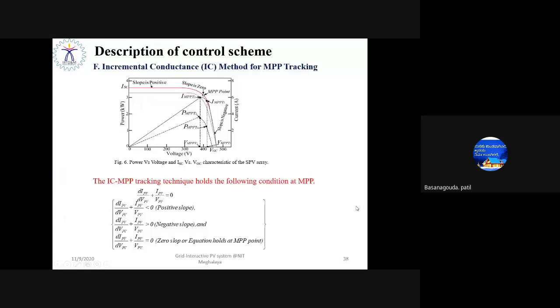Okay. Yeah, and this is the incremental conductance method. As I told you, the power being extracted from the PV array largely depends on the irradiation and temperature. So the maximum possible power extraction is not straightforward. Ultimately, we have to use a DC to DC boost converter acting as an impedance matching device. So you are able to match the load impedance with the source impedance, right? So the point at which we are extracting the maximum possible power available is at the slope here. That point is the MPPT, right?